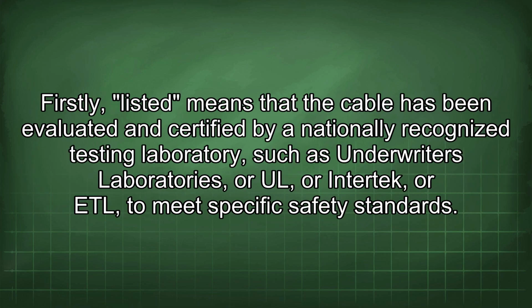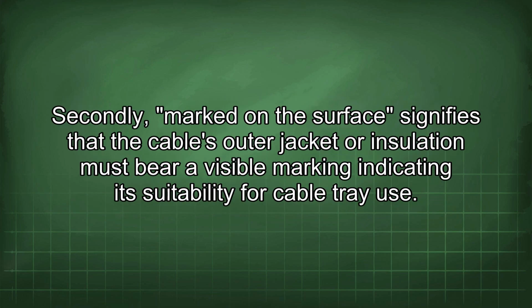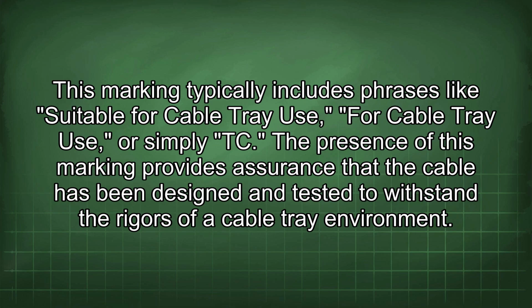Firstly, listed means that the cable has been evaluated and certified by a nationally recognized testing laboratory, such as Underwriters Laboratories, or UL, or Intertek, to meet specific safety standards. Secondly, marked on the surface signifies that the cable's outer jacket or insulation must bear a visible marking indicating its suitability for cable tray use. This marking typically includes phrases like "suitable for cable tray use," or simply TC.